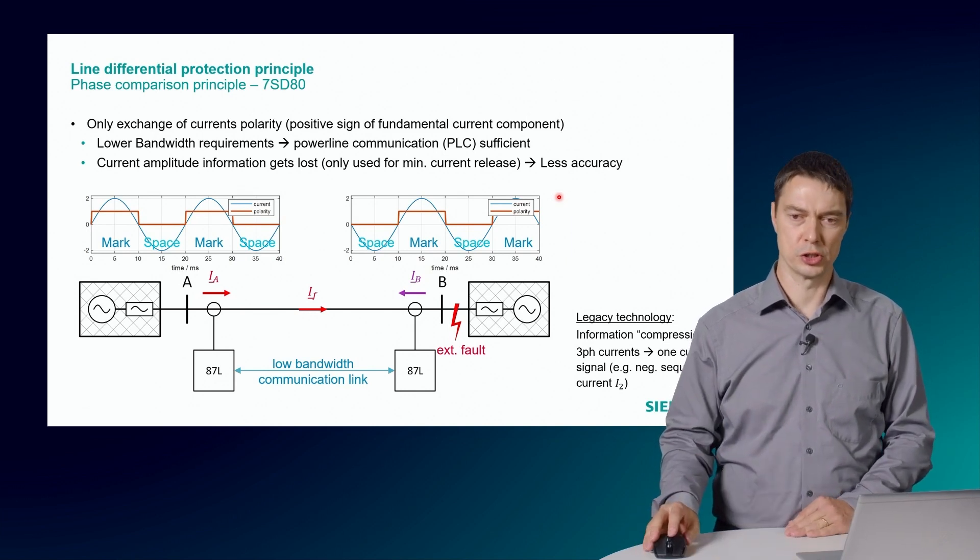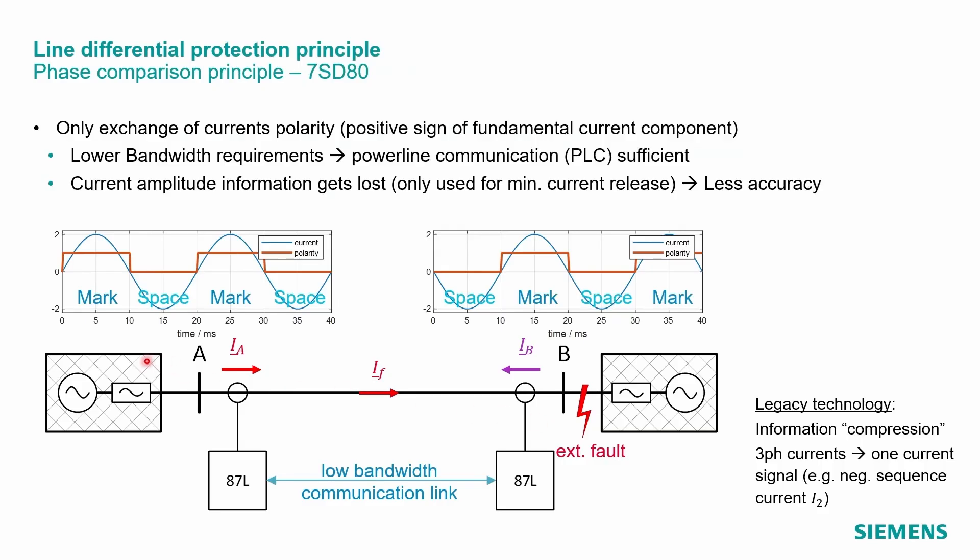In this example here, we consider an external fault condition. If the measured current is positive, we transmit a signal to the remote end, which is here called mark. Otherwise, no information is sent, space. This is done at both terminals.